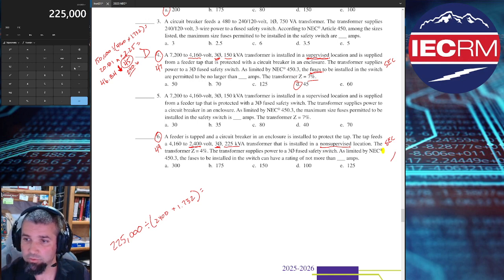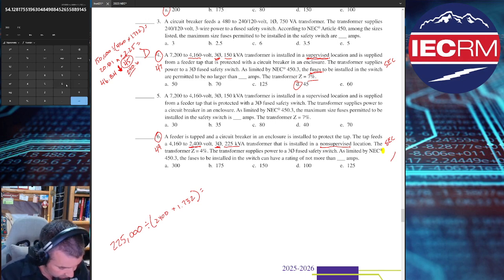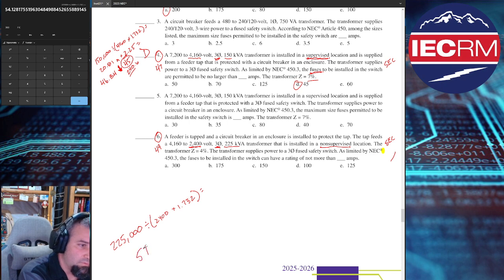225,000, divided by 2400 times 1.732 in the calculator. Close my parentheses out, and I get 54 amps, roughly. I'll just put 54 amps.